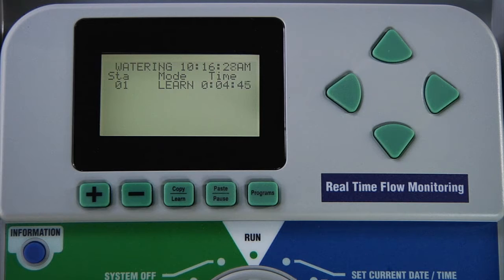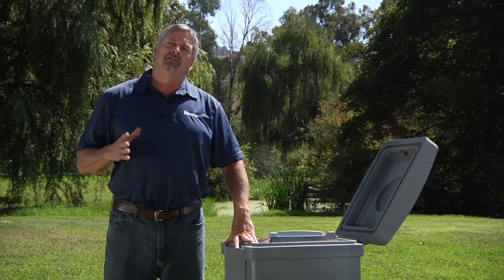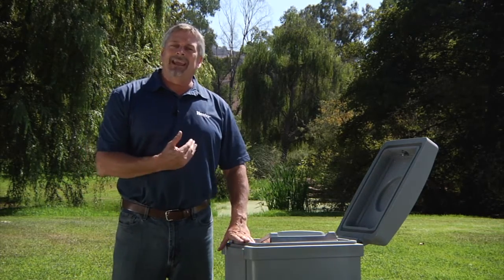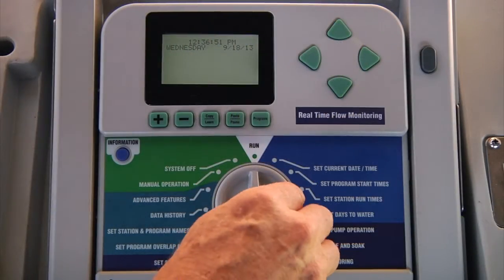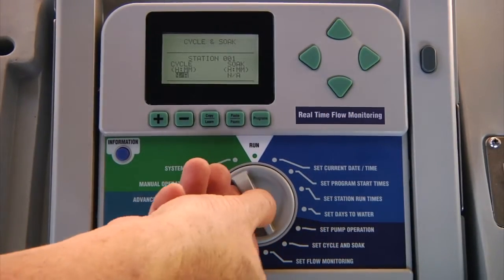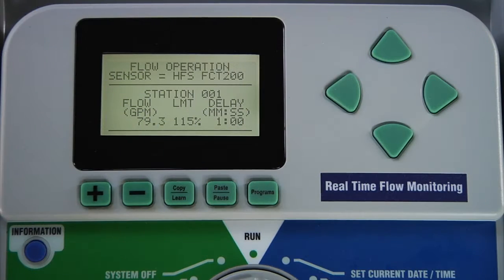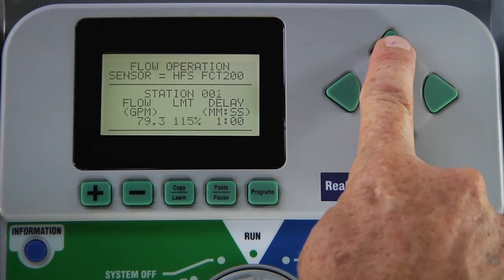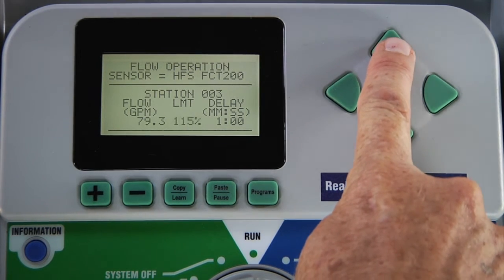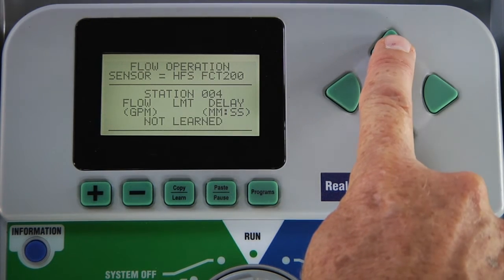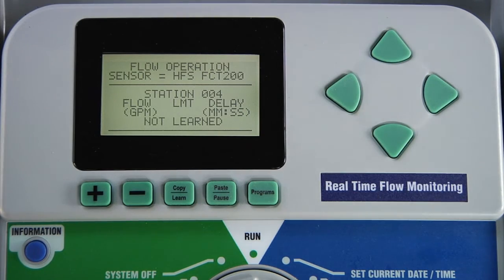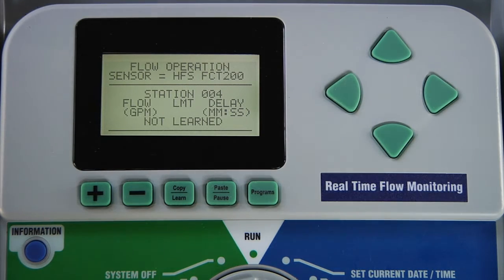Once the controller has finished learning flow values for each station, you can go back in and review those values and edit them manually if you wish. Turn the dial to the set flow monitoring position. Here you will be able to scroll through all the stations and confirm that no stations show not learned. If you see a station with this message, that's because the station did not have a run time prior to the learning process. Either manually enter the expected flow for this station or change the station to not monitored.